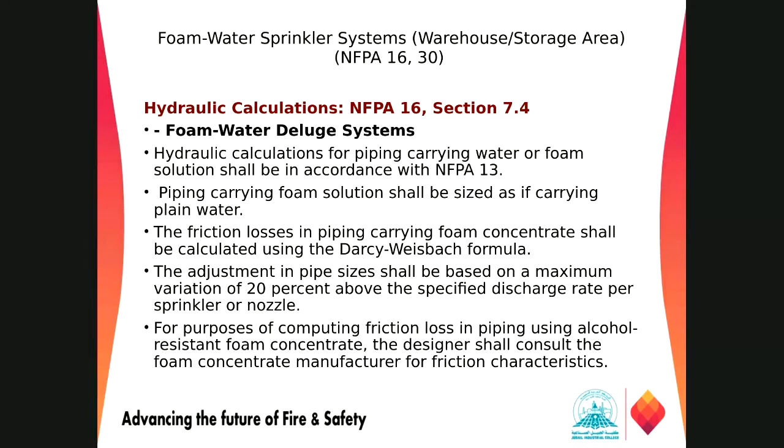And now we have the hydraulic calculation steps for the sprinkler system. It should be as per NFPA 13, because NFPA 13 has given the friction loss formulas, not NFPA 16, right? The friction loss in piping carrying foam concentrate shall be calculated by the Darcy-Weisbach formula, right?